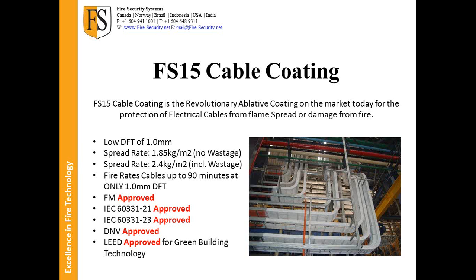So as we move down that line, the fire rated cables are rated up to 90 minutes at only 1 millimeter dry film thickness. The FS15 carries its FM approval, and it carries its IEC approvals, which are 21 and 23 for the fire rating of an electrical cable. DNV approved for marine applications, and we have LEED approval for green building technology, which is extremely good because it's an independent test which shows that we carry absolutely 0 VOCs within our cable coating. It's non-toxic and non-hazardous. So even shipping, it's not a hazmat issue. It's just a water-based coating.